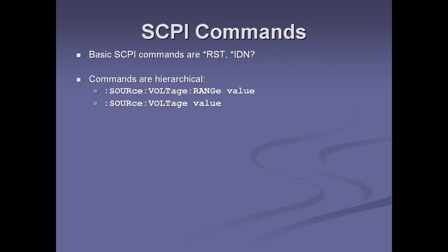The SCPI commands are hierarchical. For example, here are the commands to set a voltage range to a value, or to set the source voltage directly to a value. Notice they both use the same root commands.